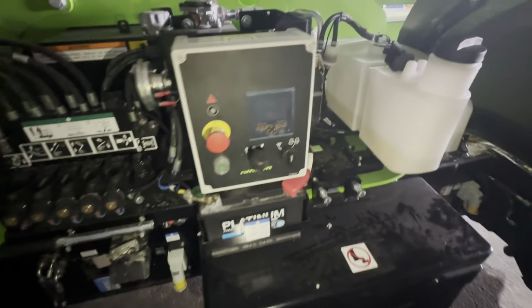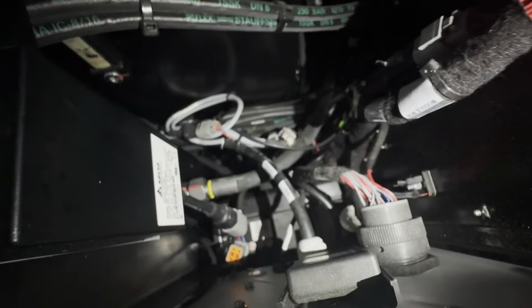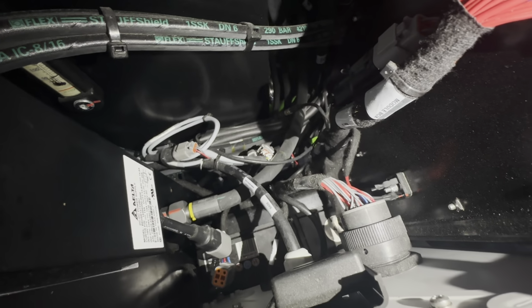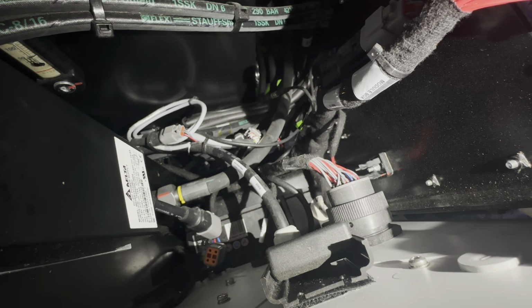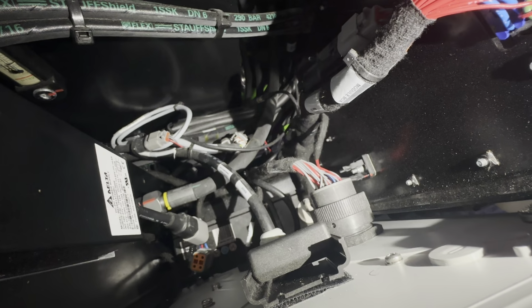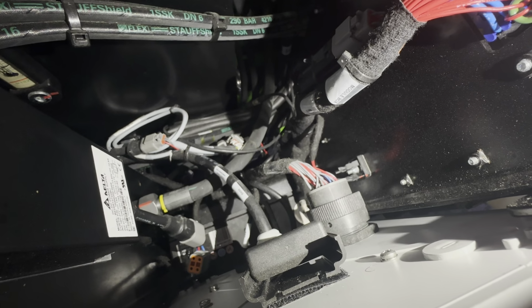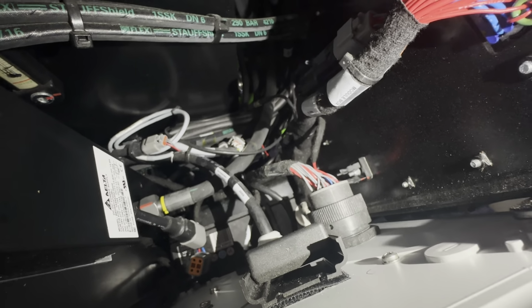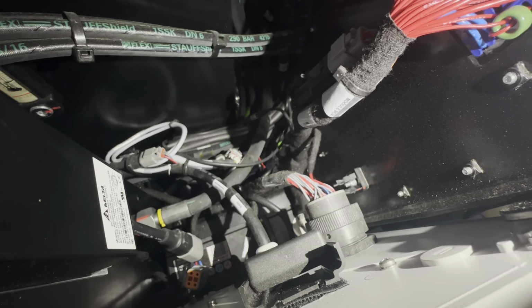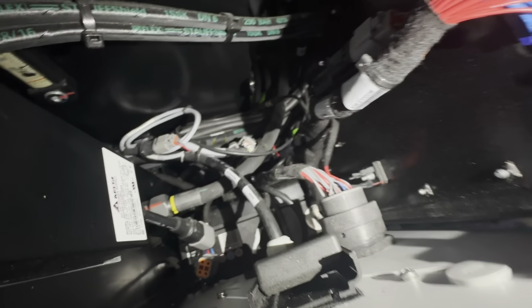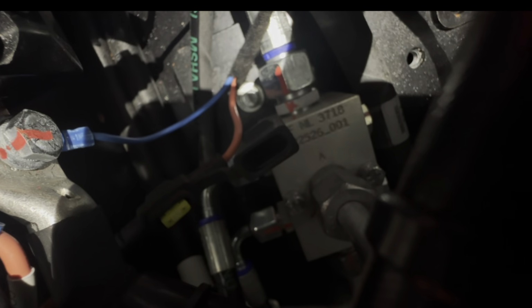Now we're going to try to start the machine up, or at least pull the isolator out, because we can't measure anything being shorted onto the positive wire. So we have to try again what we did before with a new fuse, pull the isolator out and see if we can narrow it down to this converter. Camera is set on the fuse, I'm going to switch off the light and try to pull the isolator out to see if that fuse is going to go again. Okay, 3, 2, 1.